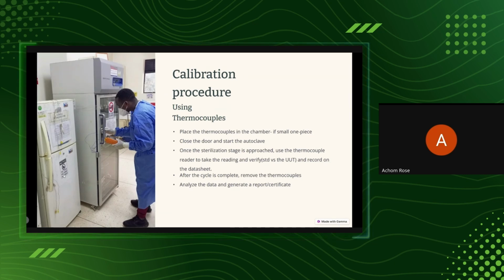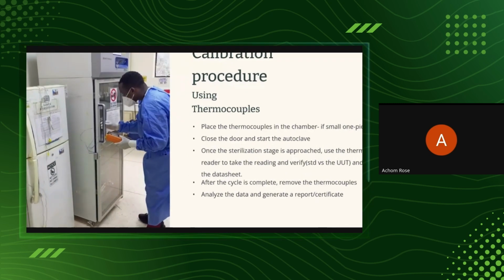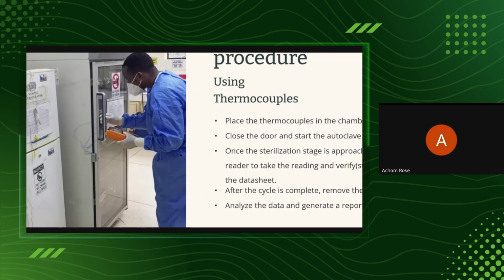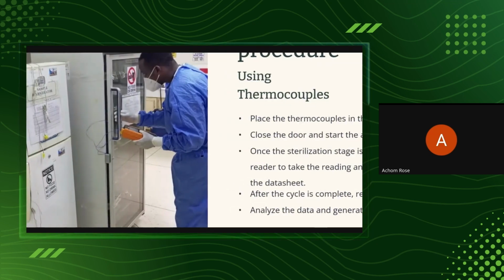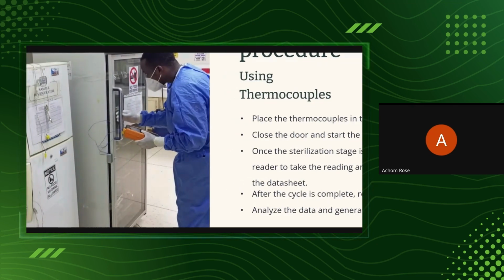You may find that you have a very small chamber. If you have a very small chamber, you can put one piece. You can put 3 pieces, maybe on the left, the middle, and the right. Or still, if it is vertical, the top, the middle, and the bottom. And then you take your readings. So like here, the person is actually taking the readings from the chamber. So you want to see at the top here, what was the reading, or what is the reading. So once the sterilization period starts, then you come and actually start this reading. Okay, so the same thing after you have recorded. So here you'll need a data sheet where you're coding your first data, your raw data that we call raw data. So you have to have a data sheet.